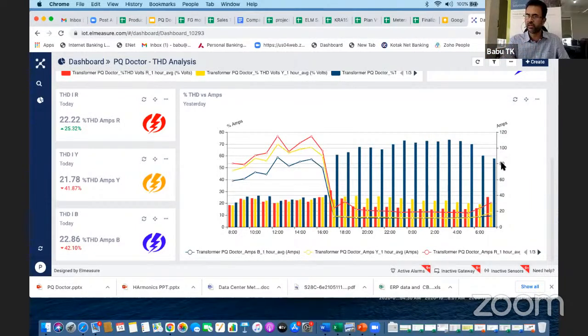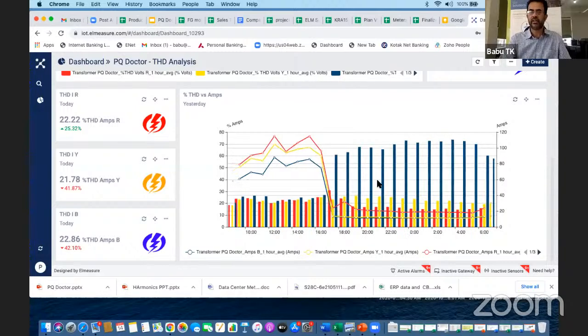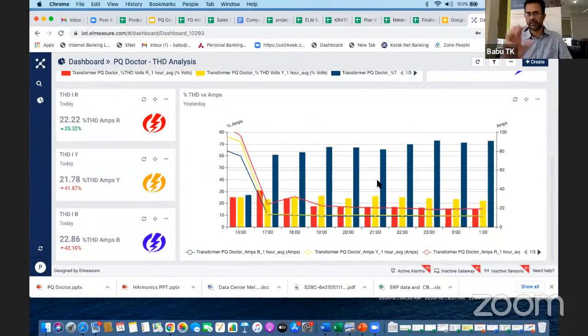So UPS is still running in the night, and that's why, though the load is very negligible, the load on the right side and left side is the THD percentage. So if I look at the load, it's very negligible, about 20 amps in the night, whereas I have a huge THD percentage in the Y phase because I connected my UPS there. Whereas I don't have much problem with other things. So we could see this, and we can also expand it and see where the problems are. We can do that very comfortably.